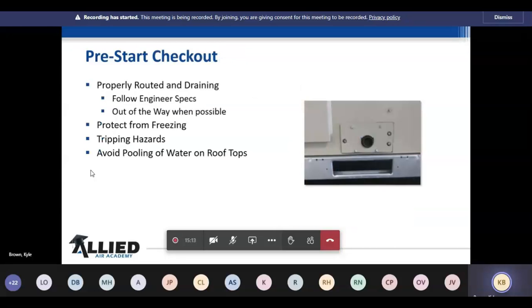One of the most overlooked, and because it's so simple, a lot of times we look at things and the simple things we take for granted, is properly draining these units, putting the right traps in. I've seen these things where they try to drain 5 or 6 units into one trap, and that one trap can't handle all of it, and it backs up. And when these things are on a rooftop and it does any damage to the inside of the building, and if it's a department store or a restaurant or a bar, especially a bar, when they put a lot of money into fixing up that bar and have it pretty, and then water dumps in on it, it costs a lot of money to repair that.